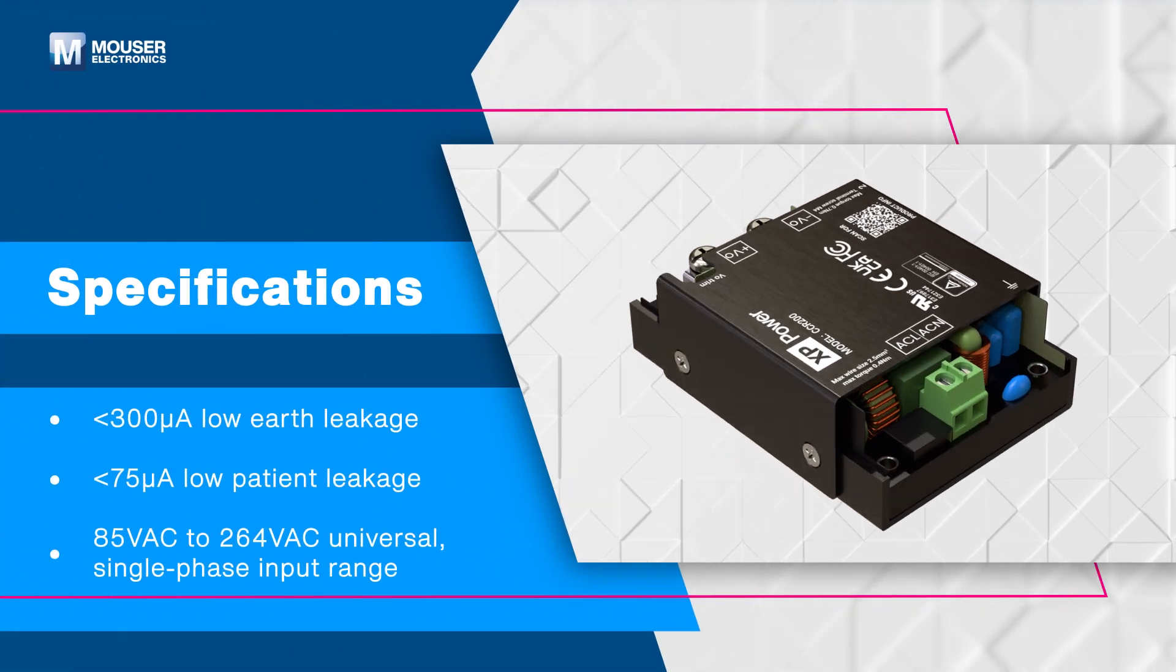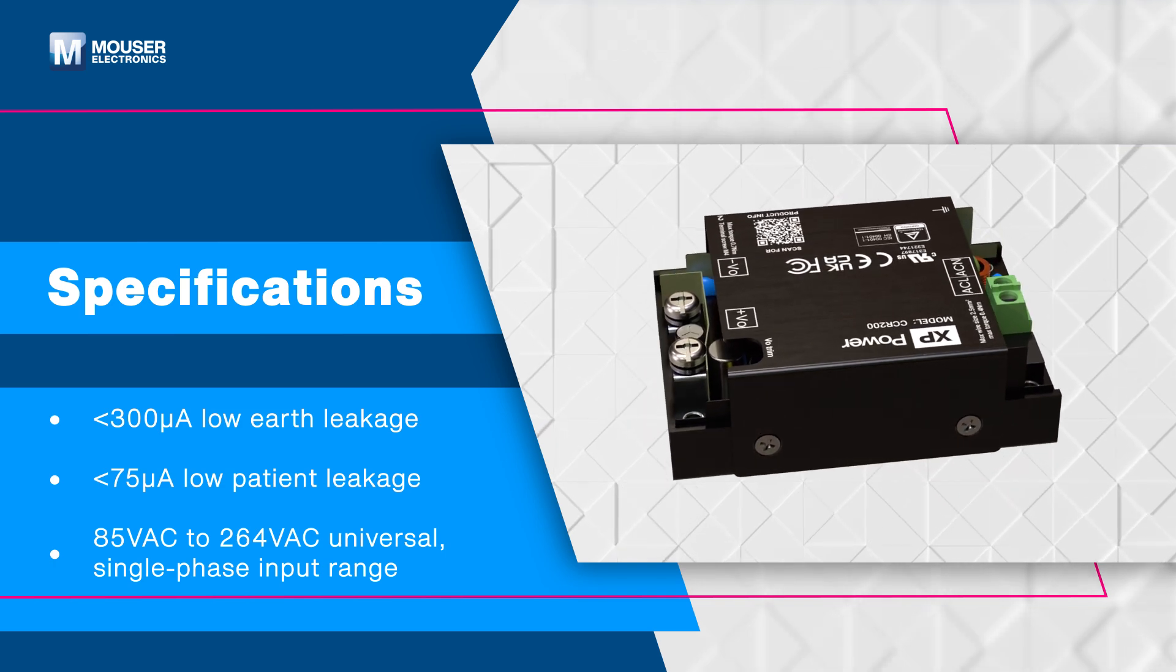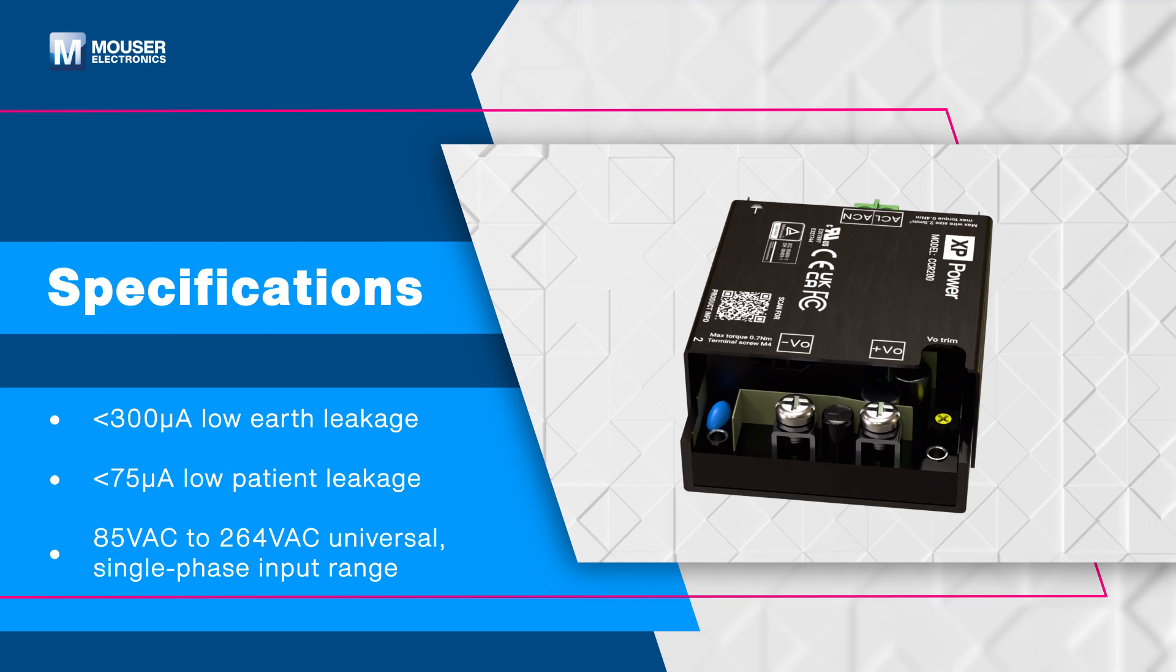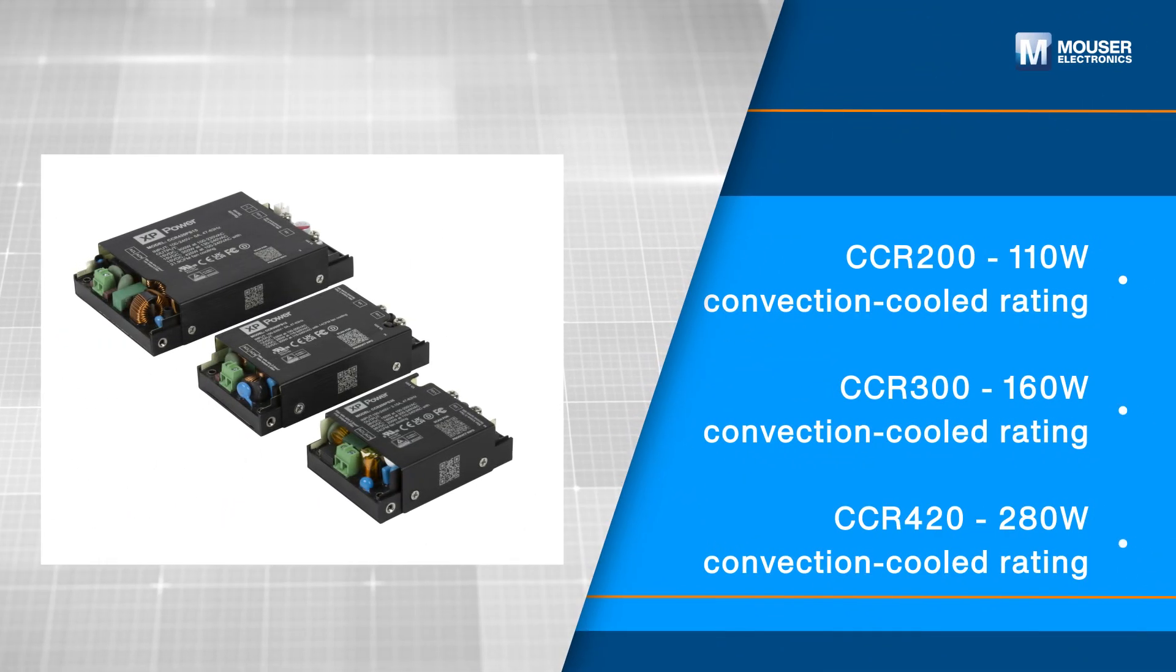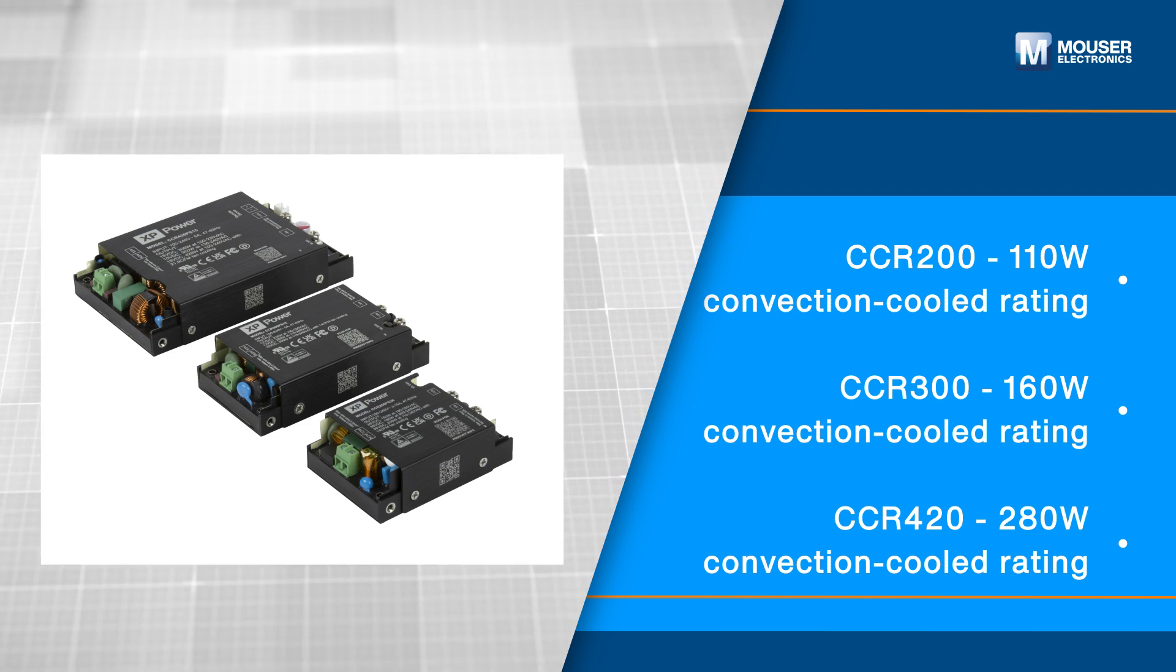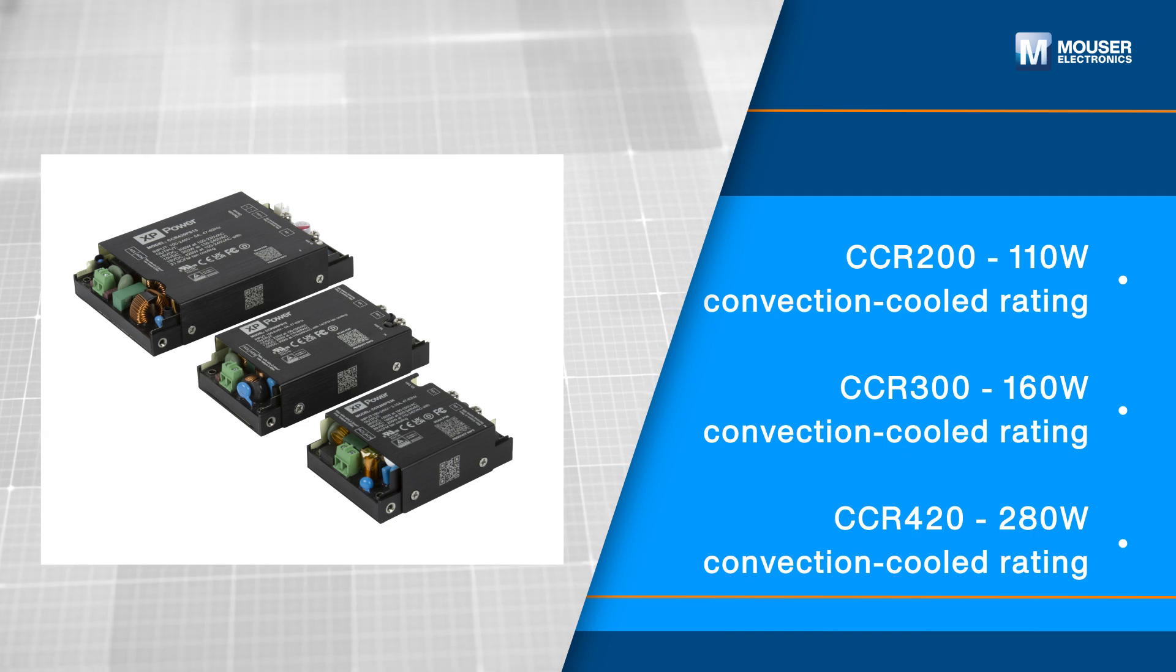These power supplies offer low earth leakage less than 300 microamps and low patient leakage less than 75 microamps with a universal single phase input range of 85 volts AC to 264 volts AC. The power supplies deliver 110 watts, 160 watts, and 280 watts convection cooled power ensuring efficient performance across various power demands.